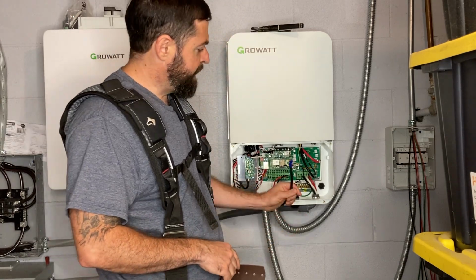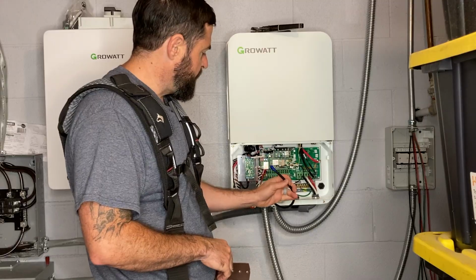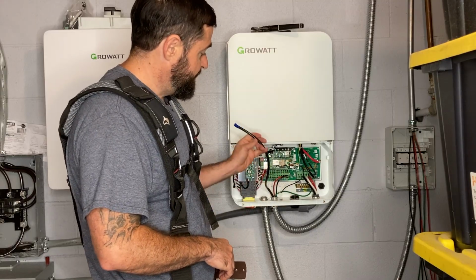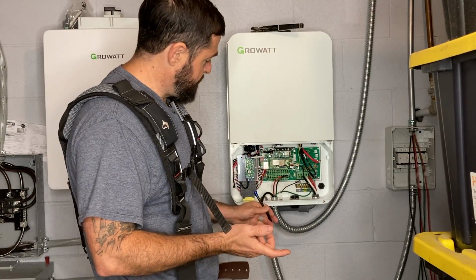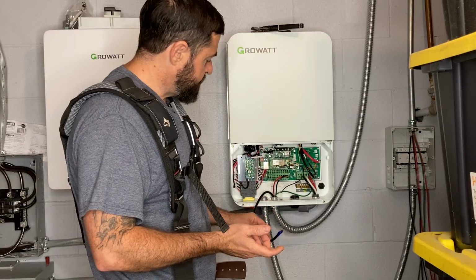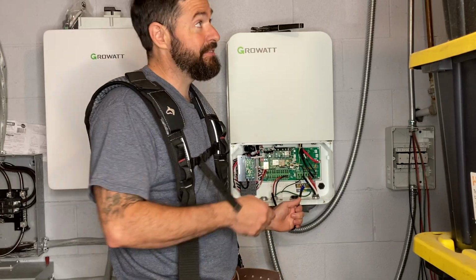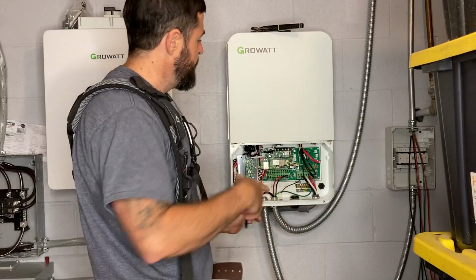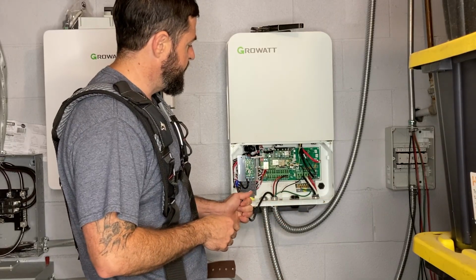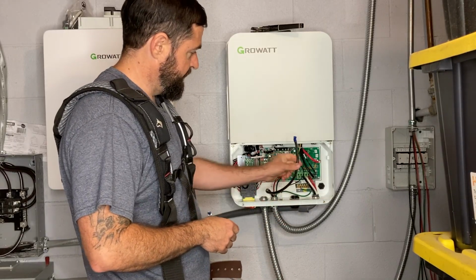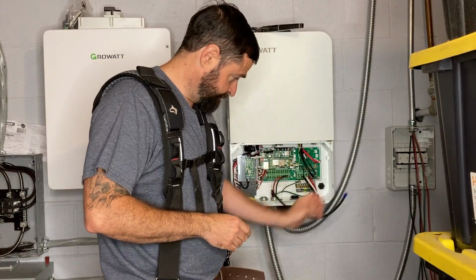So I'm gonna have to abandon this RS485 cable. This stuff is expensive, and unfortunately I already pulled it through the conduit. So I'm just gonna pull a Cat 5 cable external to the conduit between the battery and the inverter, and just kind of leave this capped off for now in here.